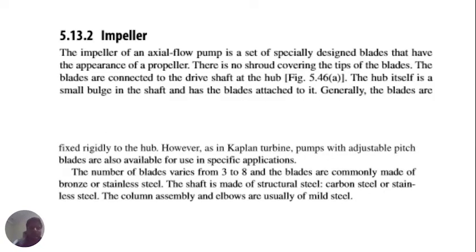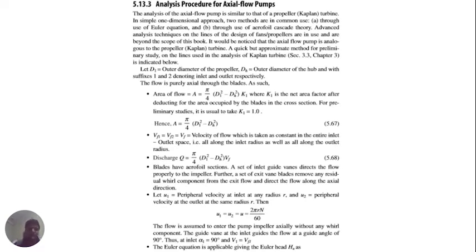The impeller of an axial flow pump consists of a set of specially designed blades with the appearance of a propeller. There is no shroud covering on the blade tips. The blades are connected to the drive shaft at the hub, which is a small bulge in the shaft. The blades are generally fixed rigidly to the hub; however, in Kaplan turbine pumps with adjustable pitch, adjustable blades are also available. The analysis of the axial flow pump is similar to that of a propeller or Kaplan turbine. Two methods are in common use: through the Euler equation, and through airfoil cascade theory.